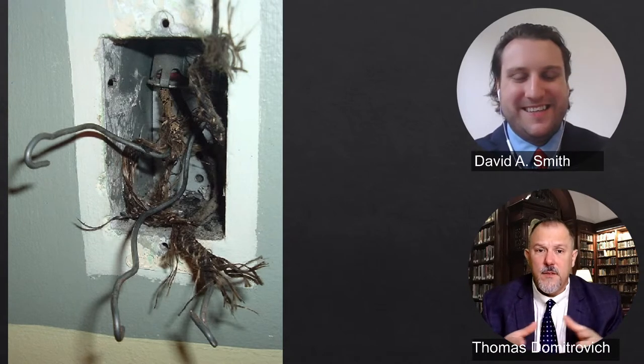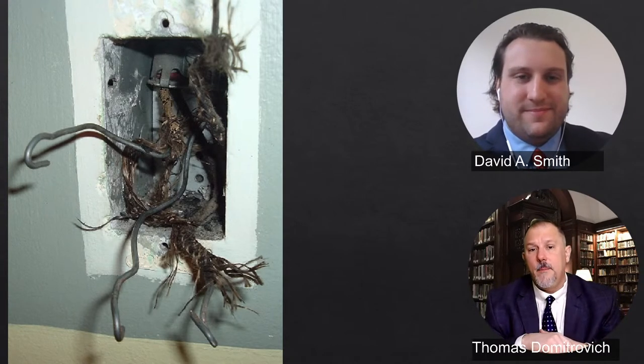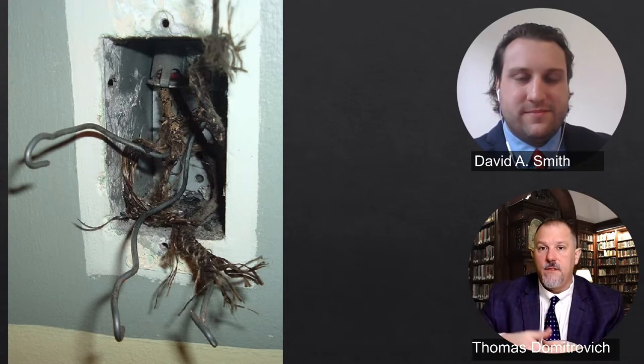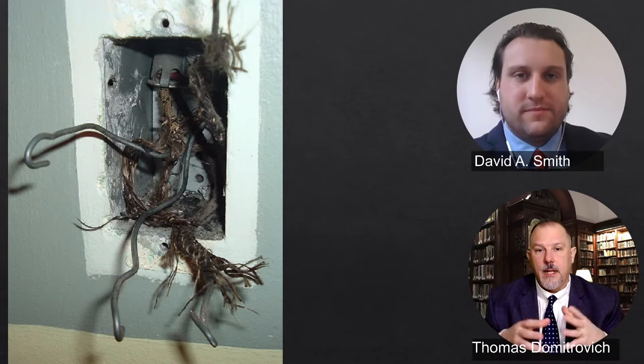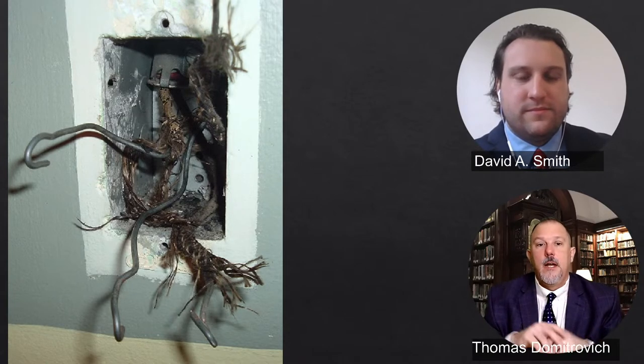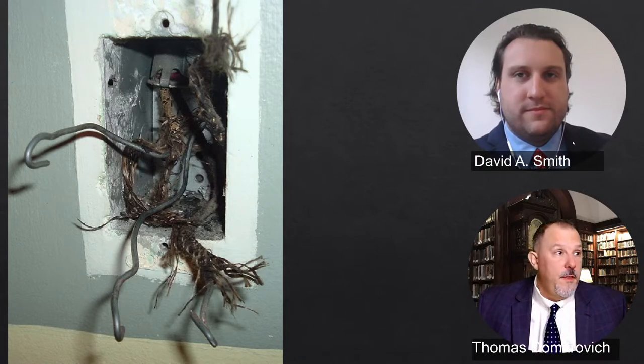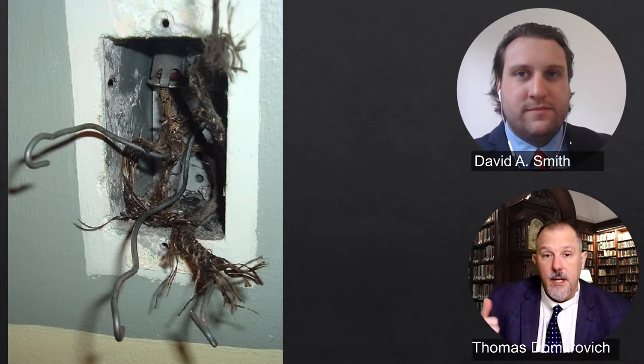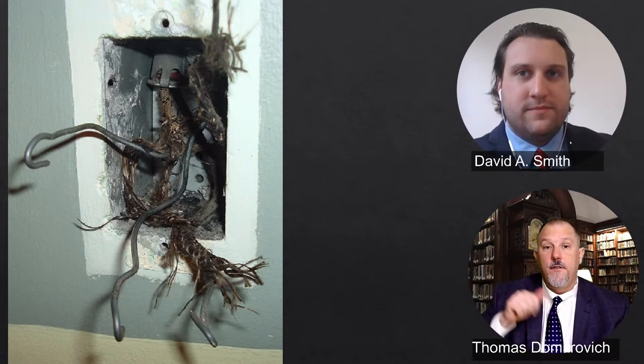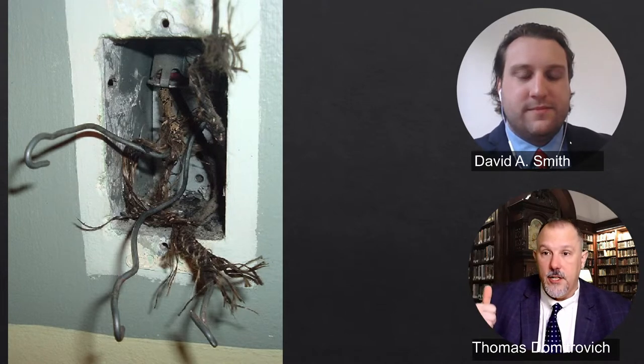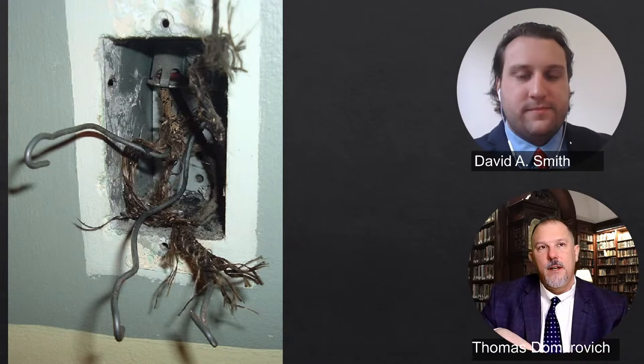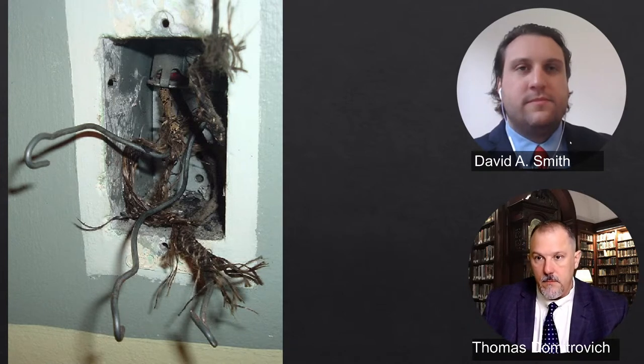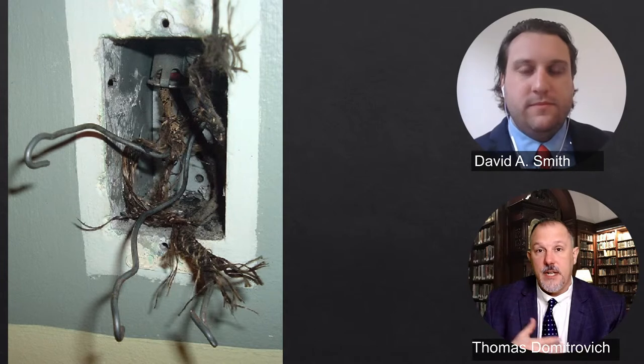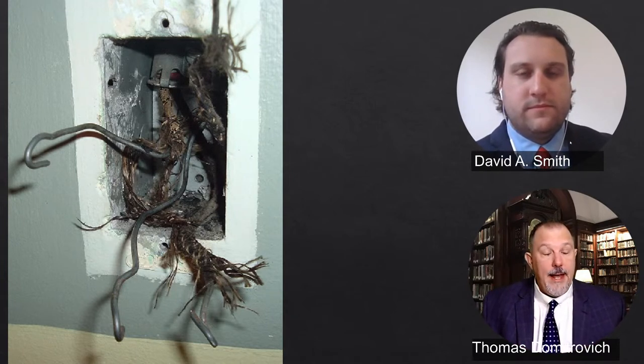I think that's just because of the location of where that circuit was run. We ended up, the AFCI was a branch feeder at the time which had ground fault protection of equipment, so we had a lot of leakage current going all over the place in this house. We had to pull a new circuit for this specific installation. I have another picture coming up of another example of a wiring issue we caught with an AFCI. Again, our branch circuit AFCIs came with 30 milliamp ground fault protection of equipment. So a lot of problems I've seen historically in the AFCI world of tripping had to do with leakage currents, and it was problems like this.